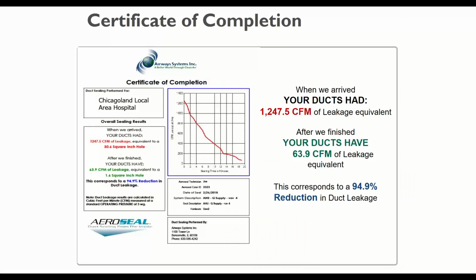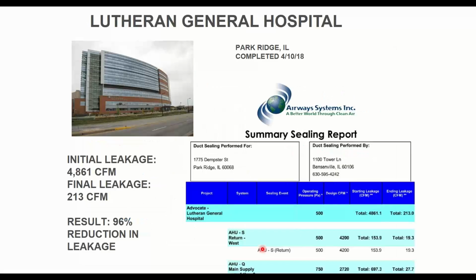Some hospitals do want to stay anonymous. So this is just a generic hospital in this case. Other hospitals are cool with us mentioning their name. But this one went down from 1,200 CFM, excuse me, down to 64 CFM of leakage when all was said and done. Another 95% reduction in leakage. You can see the theme is 92, 94, 95, 96, 99% reduction in leakage all day long.